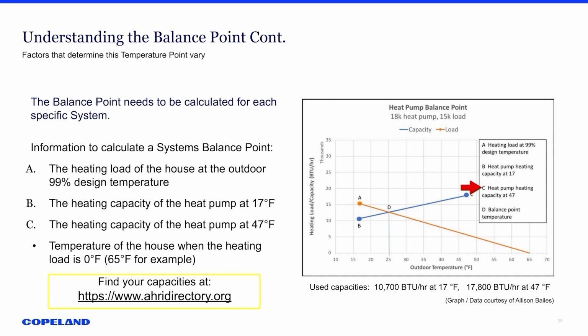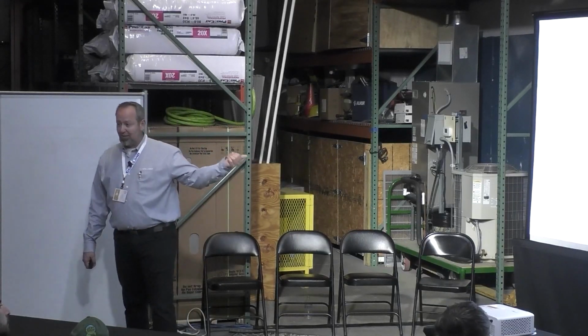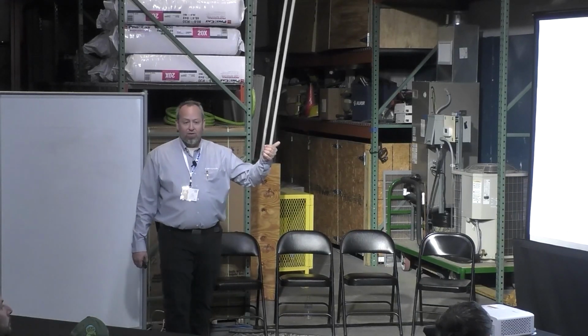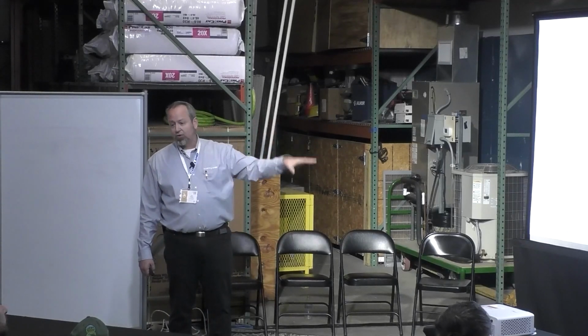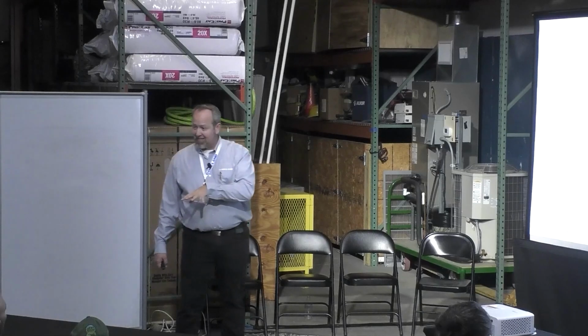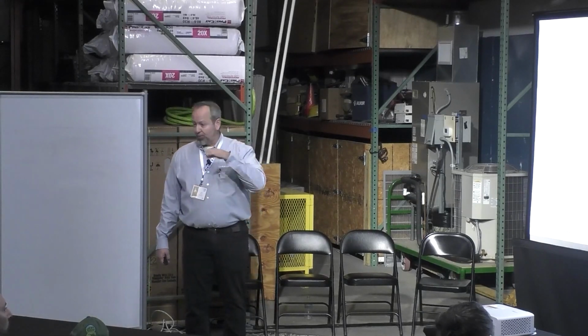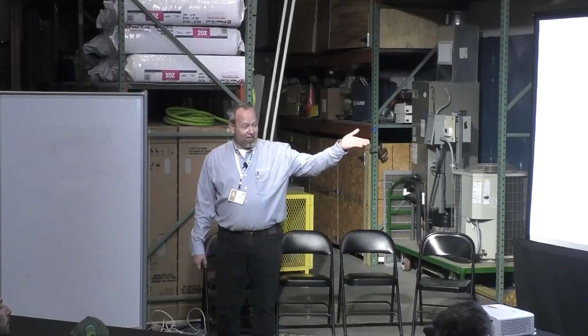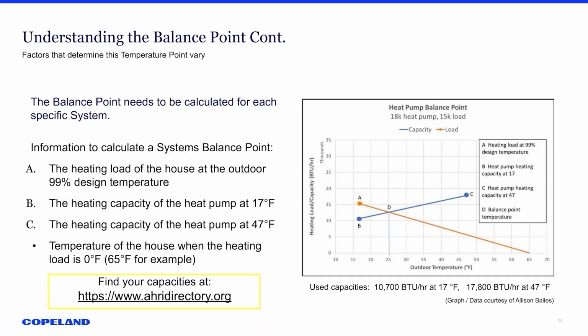You draw your lines, and D is where that balance point is, where the heat pump capacity will not keep up and the load is greater than that. That's at point D, which is a little over 25, 26 degrees. So for the balance point of this system, if you set the compressor, the outdoor unit, to shut off and the dual fuel or the inside heat to take over as first stage, you could set it at 26, and you'd maintain the temperature that you want in that house at all times.